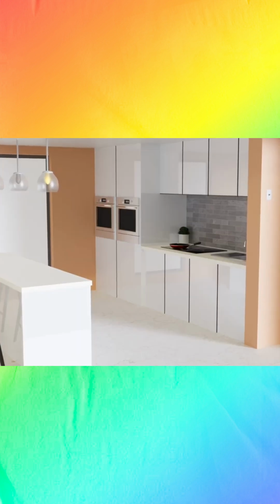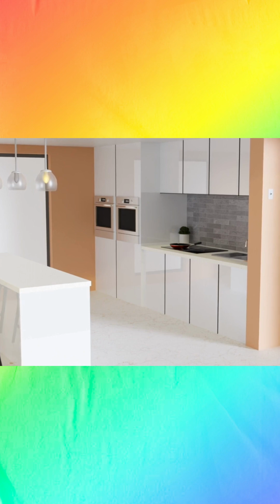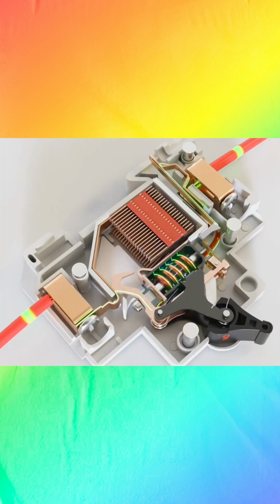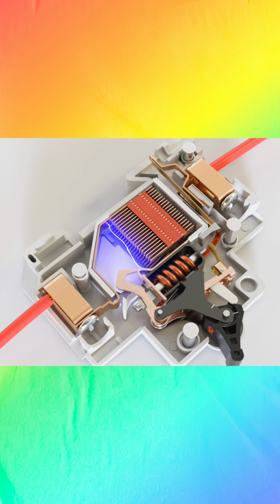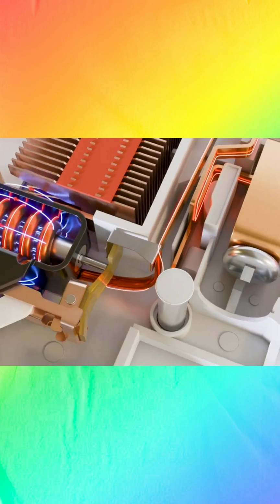Please note that a short circuit is much more dangerous than overloading. That's the reason a circuit breaker quickly trips within 2 to 5 milliseconds during a short circuit. But in case of overloading, it takes a few seconds to trip.